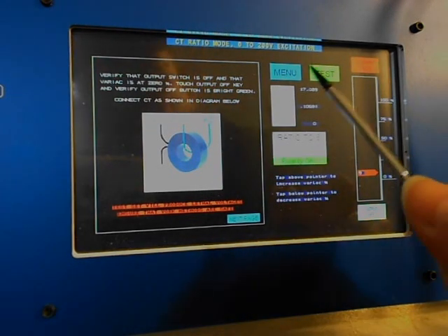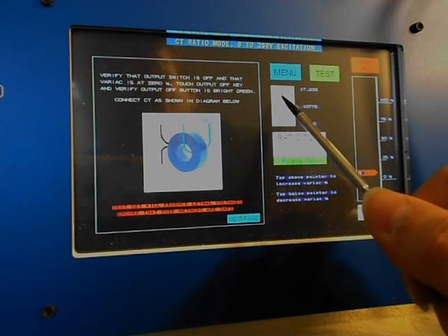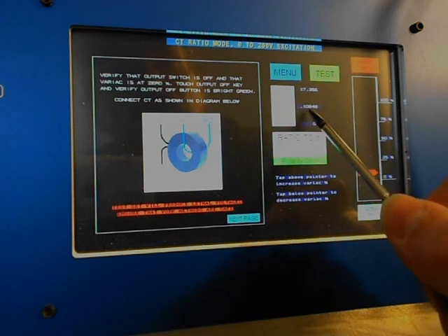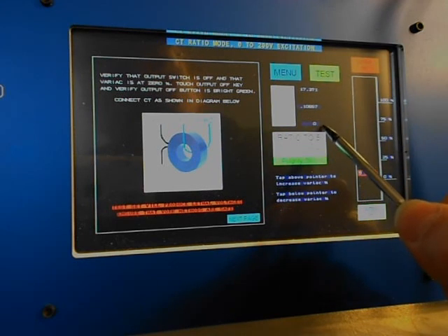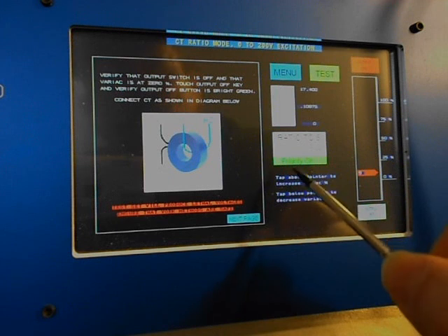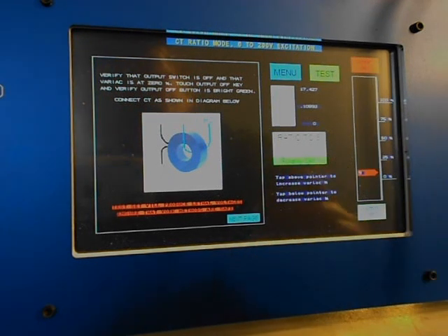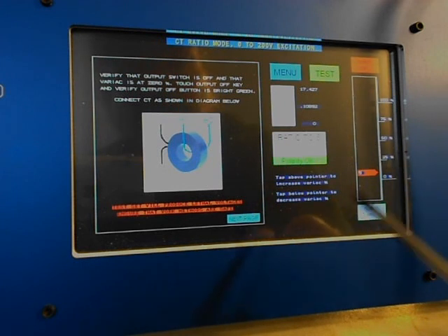As you can see here, I get the output XV voltage right here. It's 17 point something. The input HV is 0.10845. The angle is 0, which determines the polarity, and the ratio here is 799.98. Okay, and that's all I need to do.